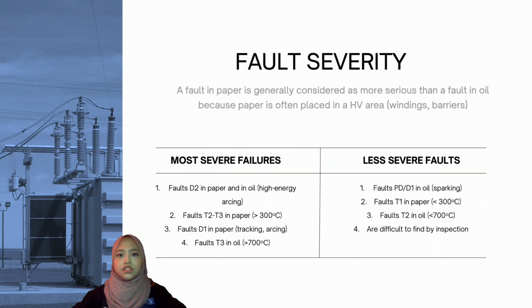For less severe faults, first, fault PD or D1 in oil, sparking. Second, faults T1 in paper, less than 300 degrees Celsius. Third, fault T2 in oil, less than 700 degrees Celsius. And lastly, fourth, faults that are difficult to find by inspection.